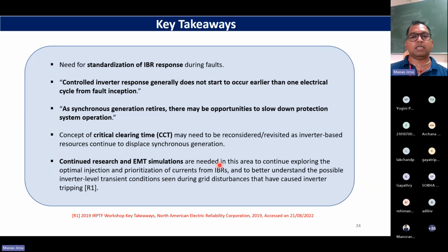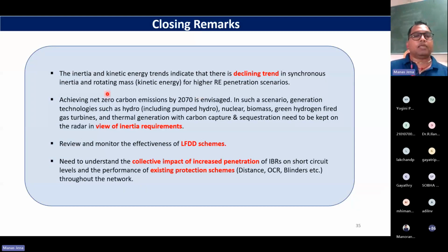So EMT simulations are needed in this area to continue to explore the optimal injection and prioritization of the currents from the IBRs, and to better understand the possible inverter level interaction during transient conditions, and how the dynamic response of the inverter control system is actually affecting the grid dynamics, monitoring and protection. A few closing remarks. The inertia and kinetic energy trends we are seeing are a declining trend, right? So inertia monitoring, inertia distribution monitoring is very important. And we need to revisit the thresholds or the settings of the LFDD and rate of change of frequency relays. We need to understand the impact of these IBR controls on the short circuit programs and the protection philosophies, all the legacy protection philosophies, distance, overcurrent, etc.